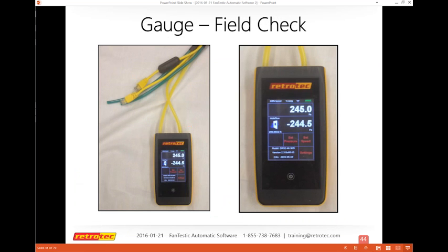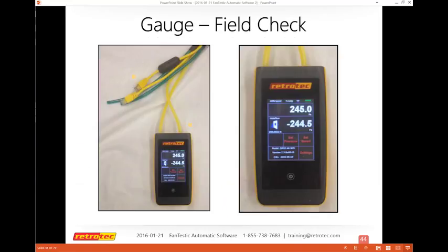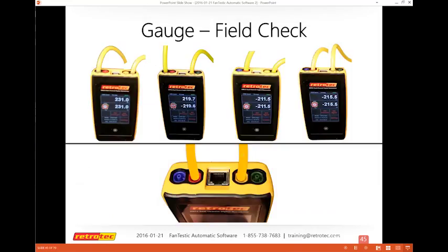There is also a form you can download to fill out a field check for your gauge, and it gives you basic information about how to connect the tubing and check the tubing. Enter this form and your name and date, and you can document that you've been checking your gauge regularly. We moved to just using the yellow tubing with the umbilical because blower doors and duct testers all have one same common length, so it's easy to check your gauge and do that.